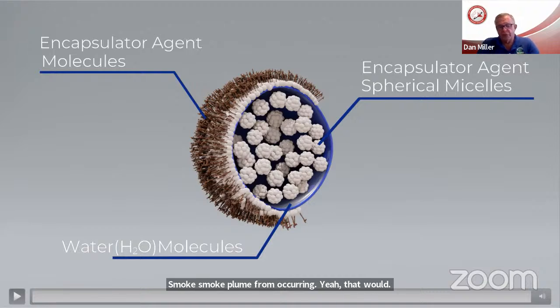The other thing it's doing is penetrating materials very well when it hits the surface. For lithium-ion batteries, for example, in cells, it's going to penetrate, soak in, and neutralize the flammable electrolyte very quickly, just like it neutralizes flammable liquids. And it's extremely resilient under that high heat to stay there and keep cooling, not vaporizing quickly like water does.